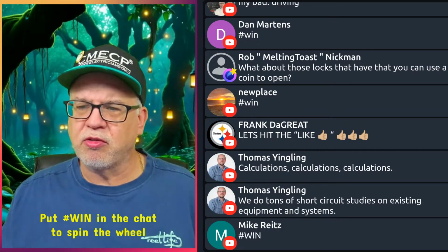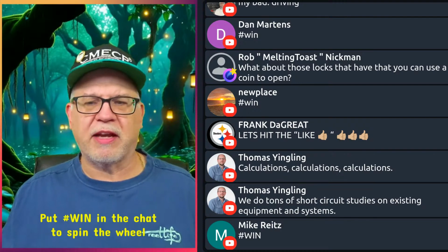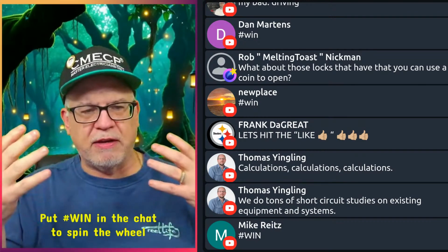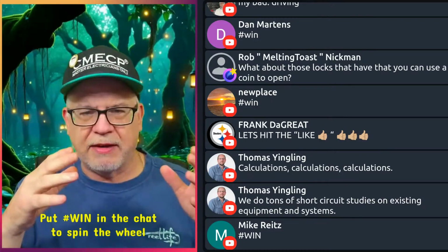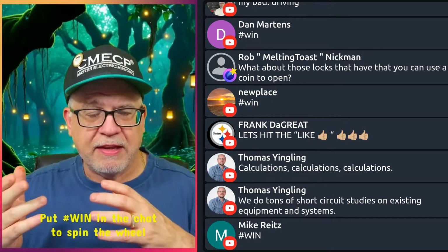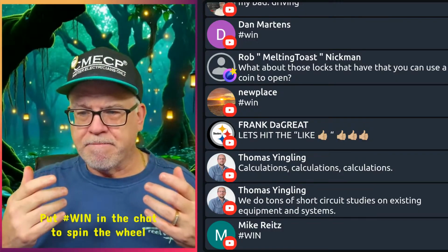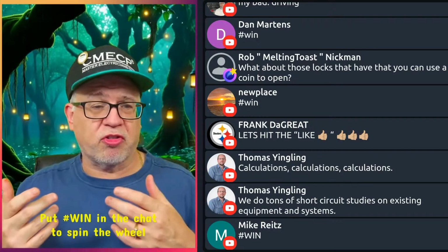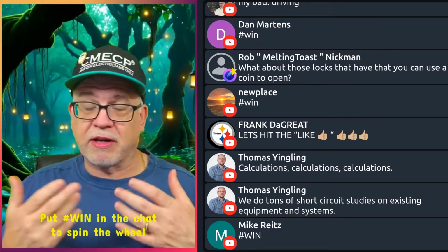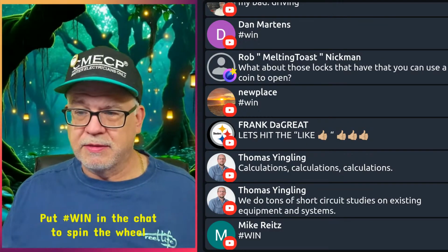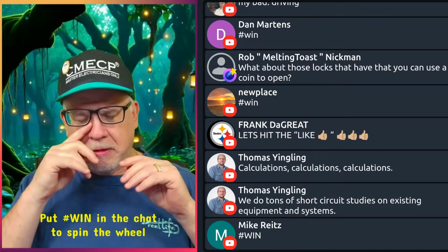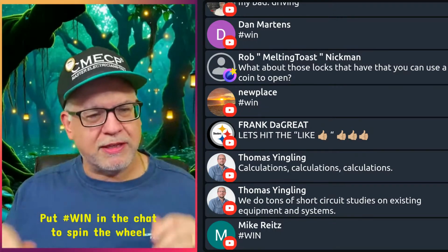So we cannot use a breaker that is not rated for an application. That's when we start looking at split and straight rated breakers and digging into these little nuances. Similarly, I can't take a breaker and use it on a circuit that has a voltage rating greater than the breaker's. That's a little different than the straight versus split rating of a breaker, but we'll probably look at that in a future episode.